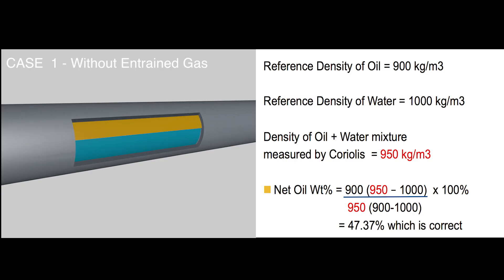Case 1: where just oil-water emulsion is flowing. We have the reference density of oil at 900 kg/m³ and reference density of water at 1000 kg/m³. The density of the oil and water mixture measured by the Coriolis flow meter is 950 kg/m³. According to the equation, the net oil weight percentage is calculated as 47.37%, which is correct.